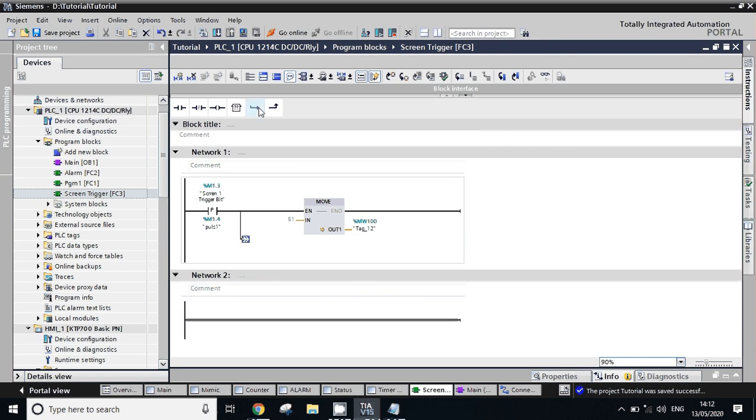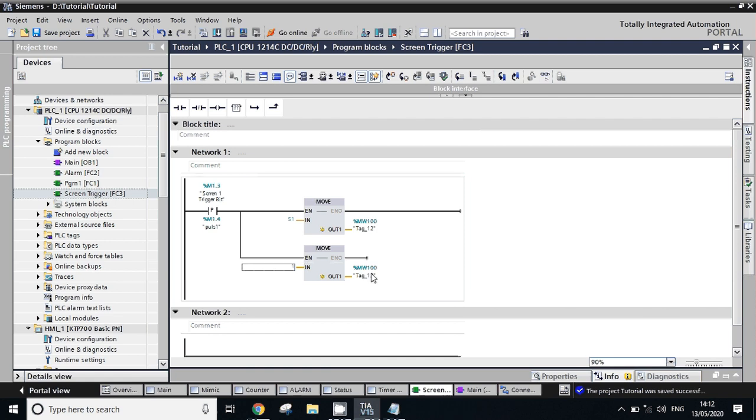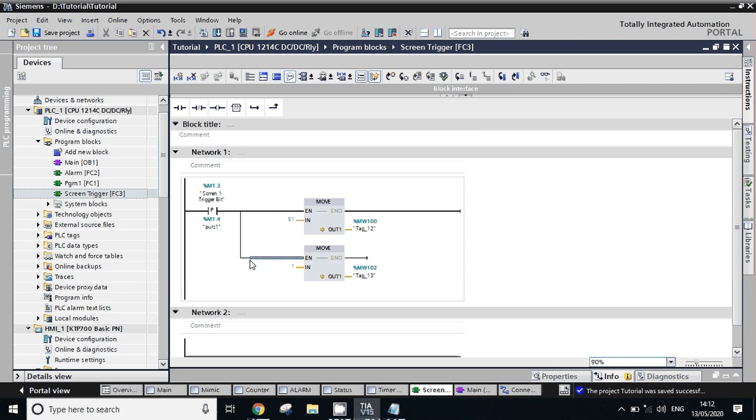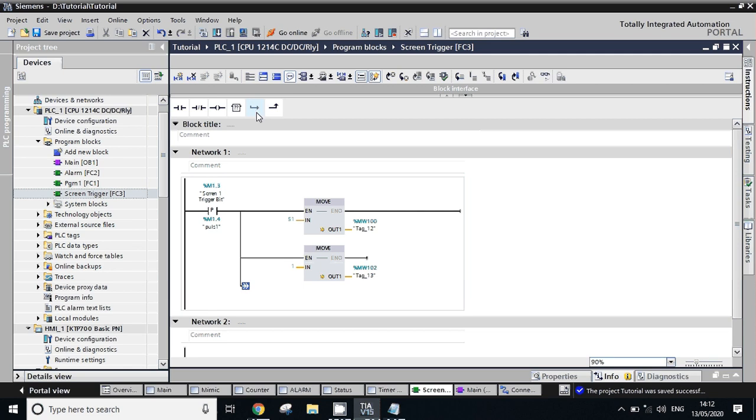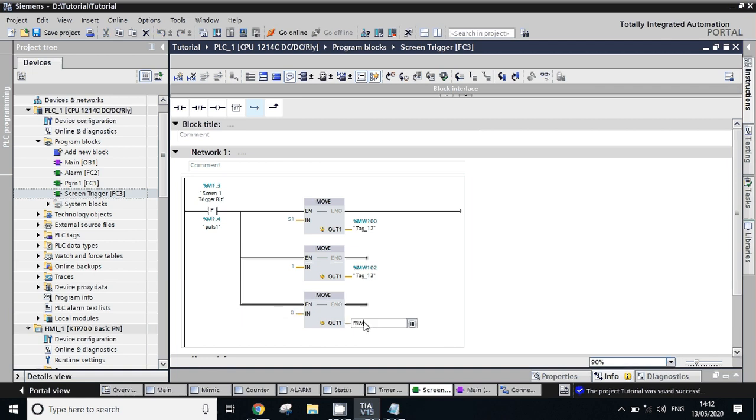So next word is MW 100, and then we'll just copy this move block, paste here. If I want screen number one I will type here one - screen number one. And here the next immediate address of word MW 102. See, I use next immediate address, this is MW 100 so next word is MW 102.